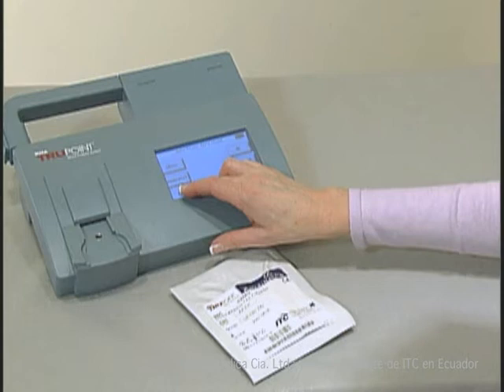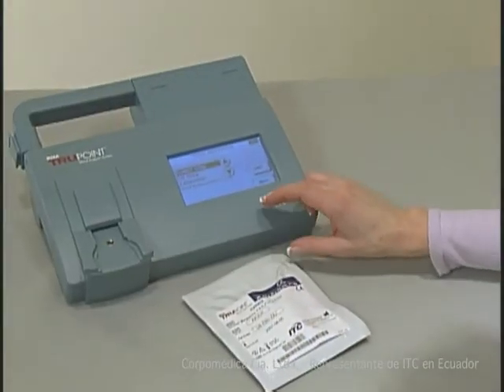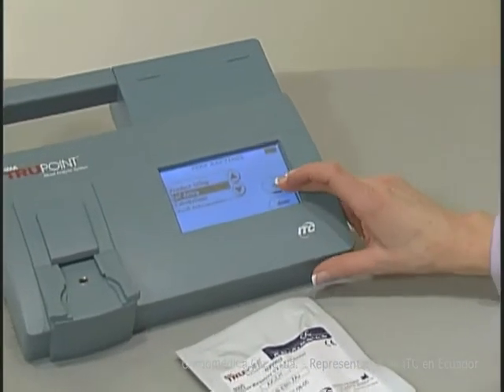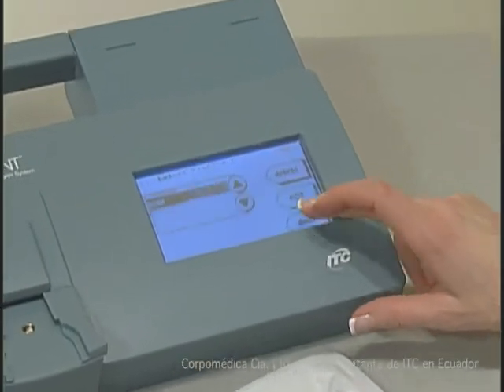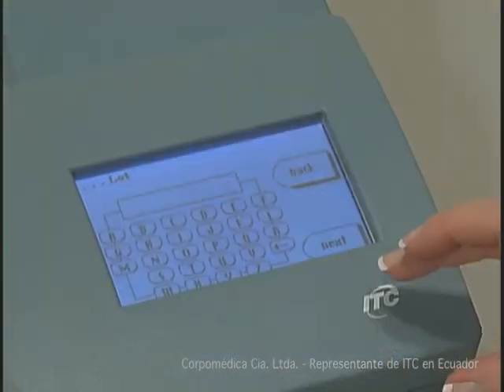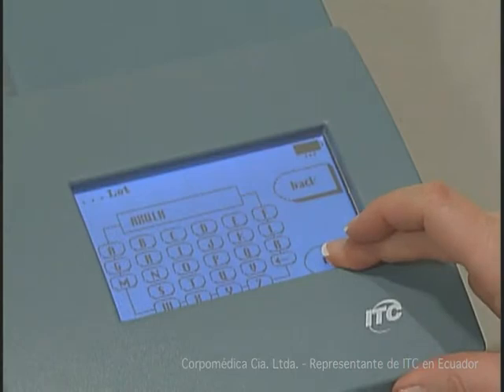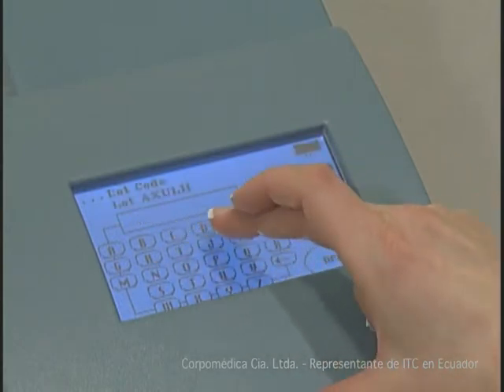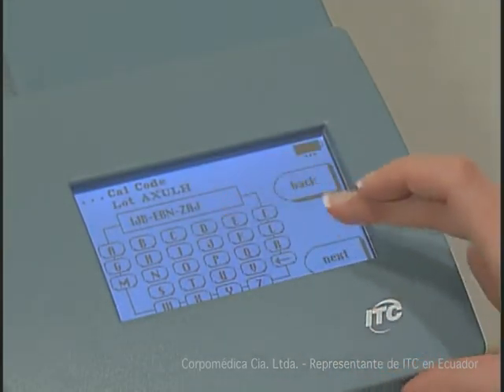To manually enter cartridge lots into the IRMA TruPoint, press Test Settings. Highlight Lot Entry. Press Edit. Select Product Type. Highlight New and press Edit. Enter the cartridge lot number and press Next. Enter the cal code and press Next. Then press Done.